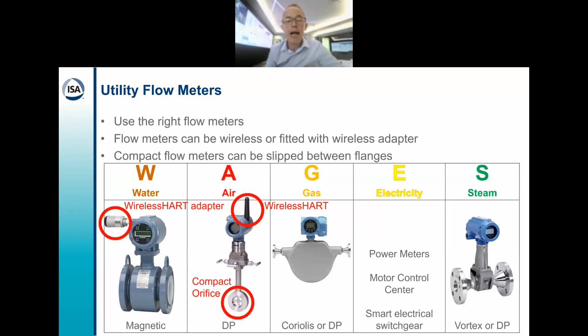A differential pressure flow meter with a compact orifice can be used for sub-metering on branches. It's very thin, so it can be slipped in between flanges by prying the flanges between existing pipe sections apart. And DP flow meters are available in a wireless HART version, meaning power cable and signal wires need not be laid. Note that other wireless technologies may not have industrial grade DP flow meters. Also, smart magnetic flow, vortex, and Coriolis flow meters are wired for power, but since they communicate HART, they can be fitted with wireless adapters, provided you use the wireless HART networking technology. So other wireless technologies may not have wireless adapters, so be careful.